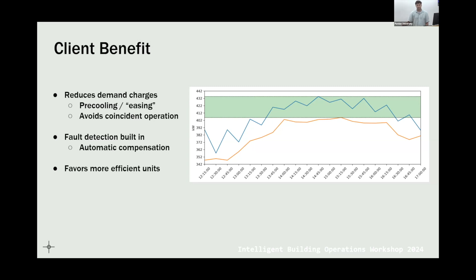The control algorithm that we implemented does do pre-cooling in order to try to bring down the temperature of the building, not in response to price signals, but just in anticipation of dramatic set point changes. So you can imagine a situation like Dong-Hoon brought up, where the building will transition from unoccupied to occupied, and all of the units will ramp up at the same time. In addition to the model predictive control, we implemented a regime at the very beginning when the building goes into its operating period, where it walks down the temperature set point.